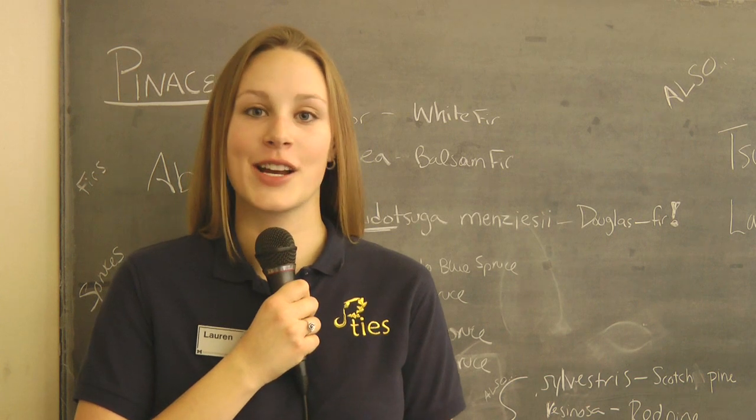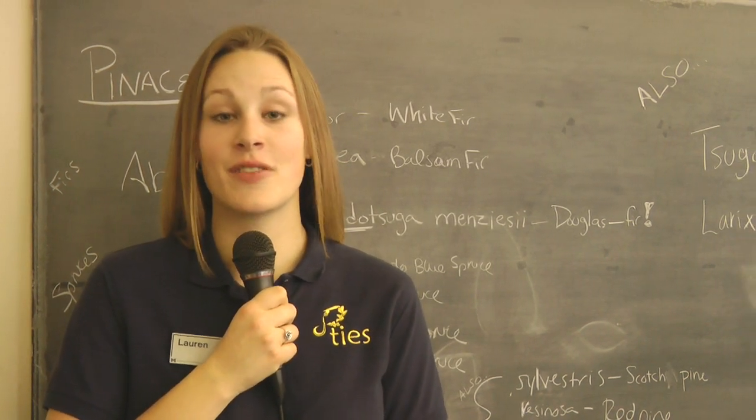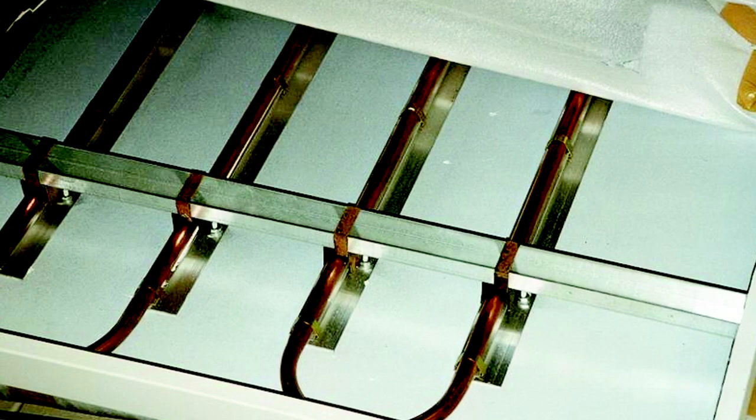Behind me may seem like an ordinary chalkboard, but it was actually a chalkboard from the original building that was saved during renovation and replaced once the renovation was complete. On the ceiling you can see panels which make up our radiant cooling system, which is the primary cooling system in the building. Behind the panels are a series of tiny tubes which carry cold water. The cold water cools the air along the ceiling, and the air sinks down where it warms up and is carried back to the ceiling to be cooled again.